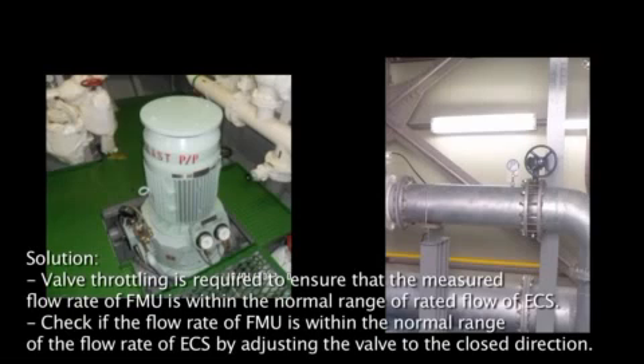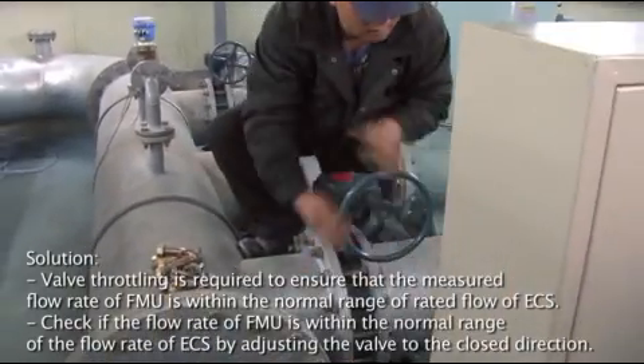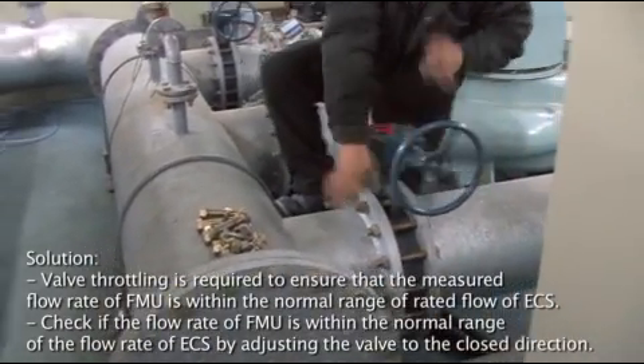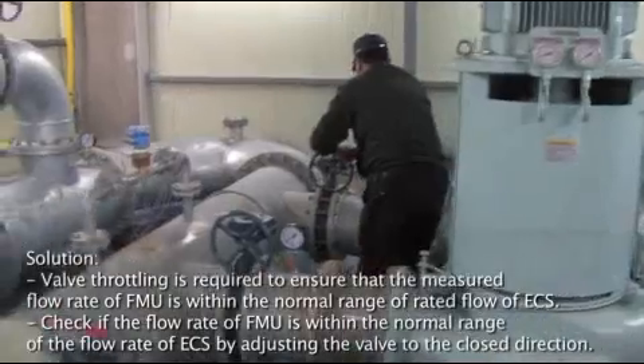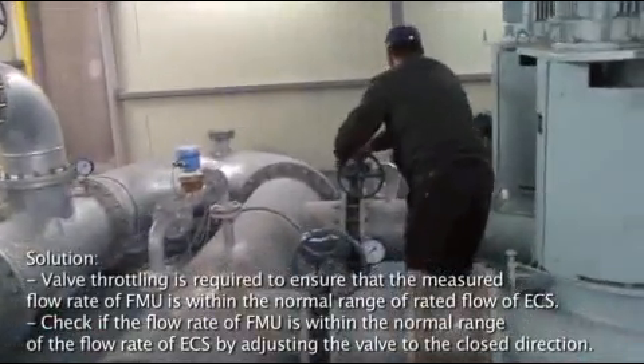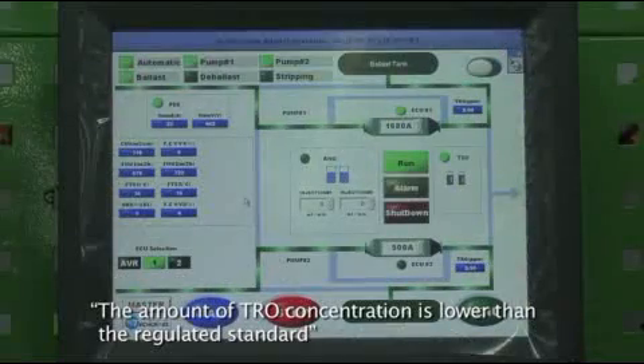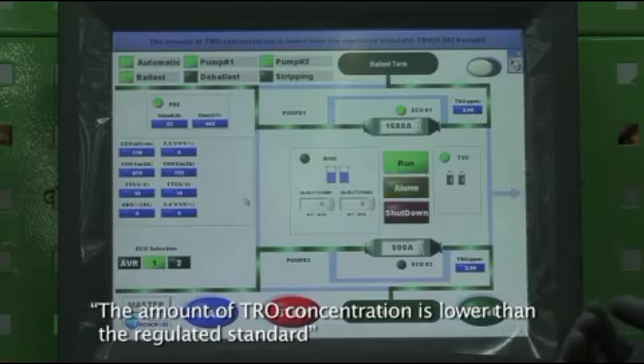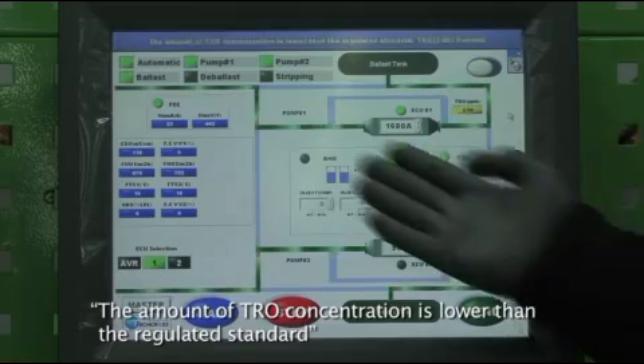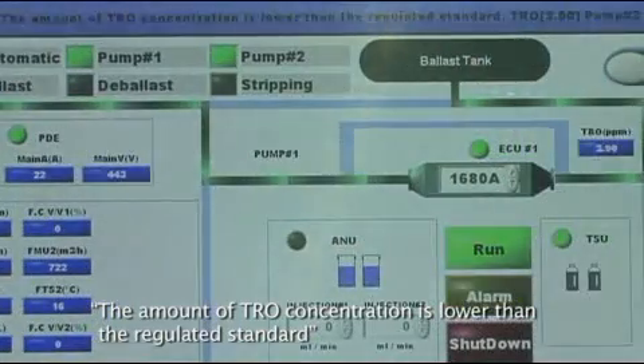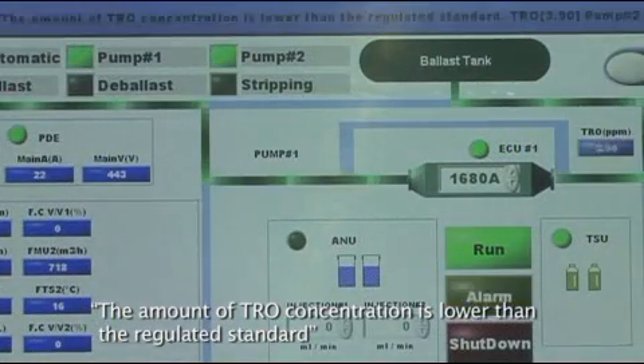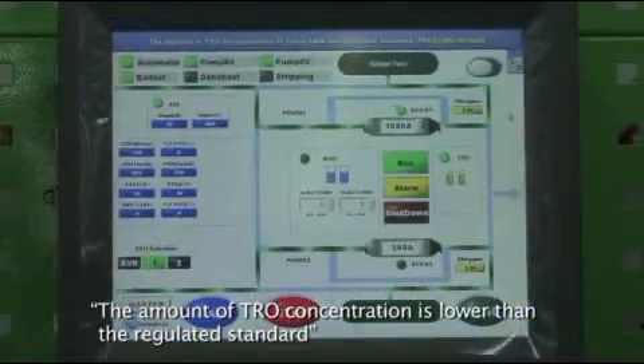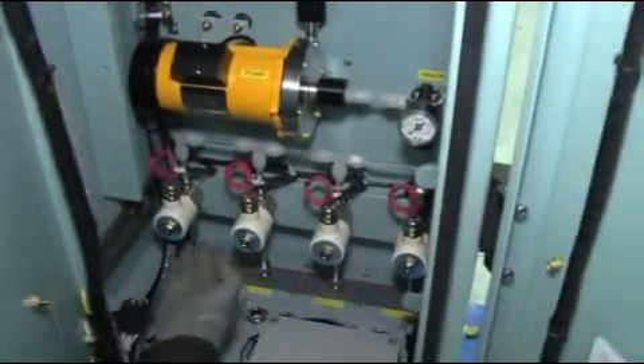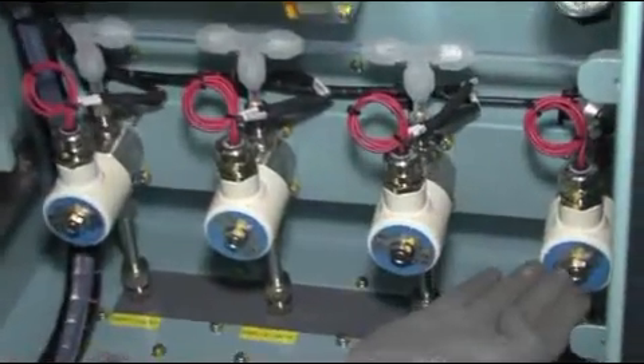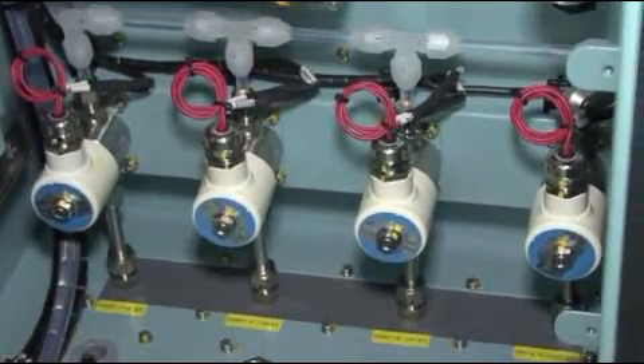Solution. Valve throttling is required to ensure that the measured flow rate of FMU is within the normal range of rated flow of ECS. Check if the flow rate of FMU is within the normal range of the flow rate of ECS by adjusting the valve to the closed direction. Problem. ECS shuts down 10 minutes after alarm message. The message "The amount of TRO concentration is lower than the regulated standard" appears. Solution. Open the door of TSU and check that sampling water has flowed into TRO sensor.